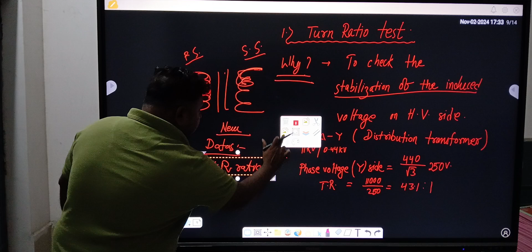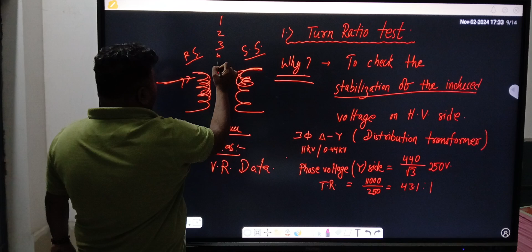There are different tappings of a transformer. Already it is known to us. We know that tappings start from 1, 2, 3, 4 and like that. It goes according to the transformer, either a distribution or a power transformer, whatever it is. It is normally from tapping 1 to tapping 17, tapping 25 even in a power transformer, and in a small transformer it is up to tapping 6 or 7. But it has different tappings, and in different tappings we have to check the voltage ratio data, whether the ratio data is the same or not.